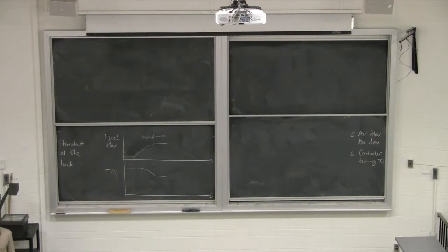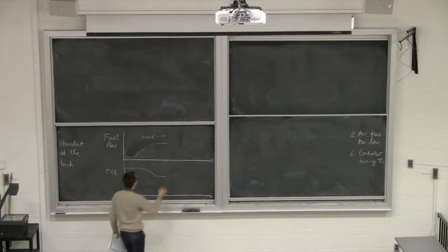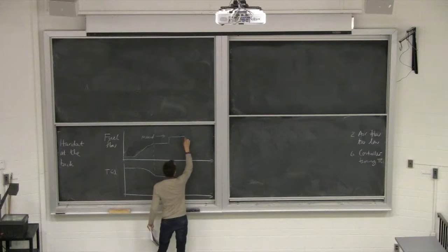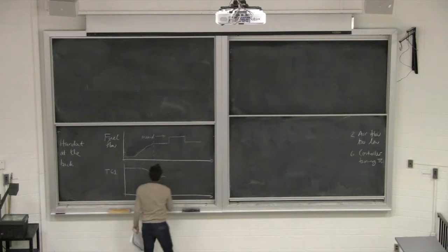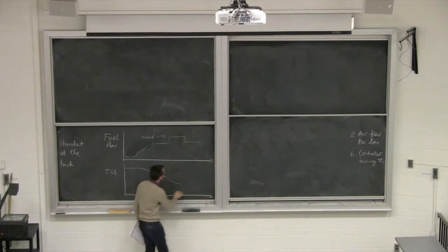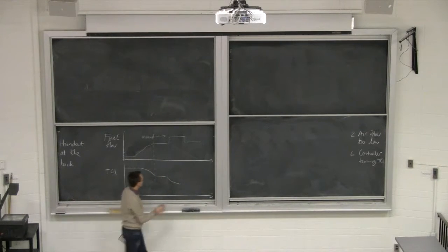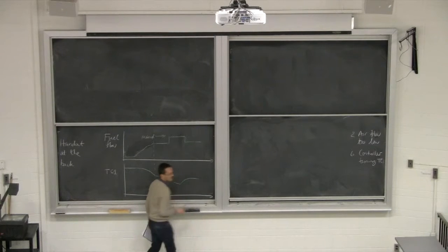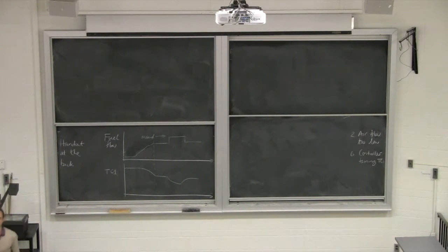Let me start this a little bit lower. Fuel flow started to rise. That was the problem. Fuel flow started to rise. And when we put the control loop in manual, we stay where we are. And then there was the suggestion to do a step test. And we stepped up and back down again. And what happened was fuel flow stepped up, temperature dropped. And then when we stepped the fuel back down again, temperature rose. And I'd ask you just to think a little bit about that at the end of the class. Why that happens.